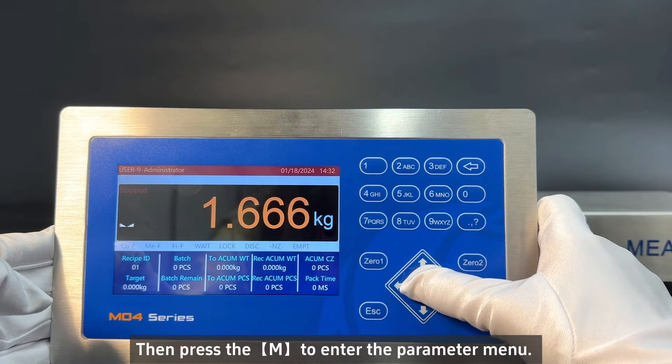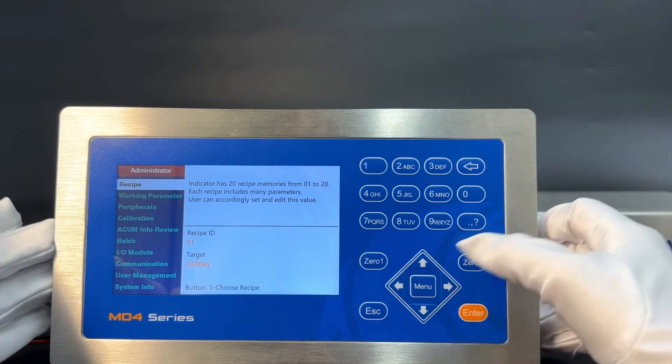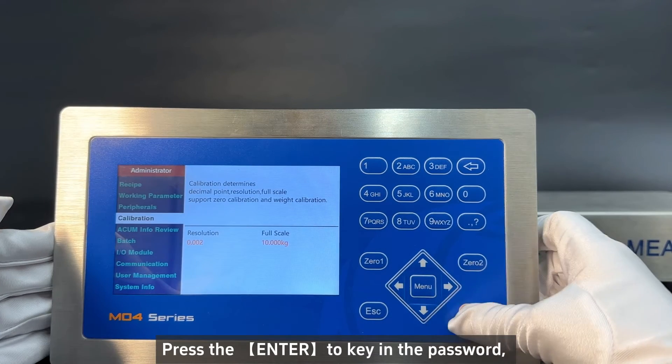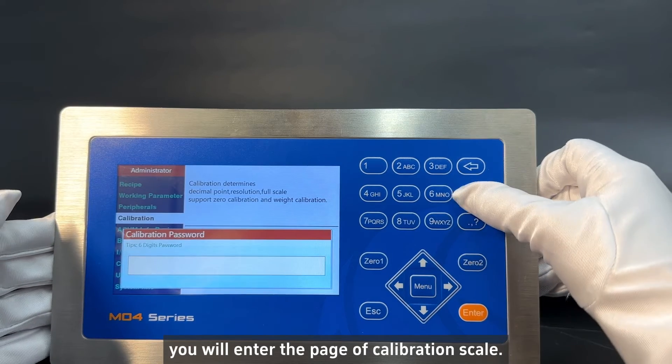Then press the M to enter the parameter menu. The calibration can be found in the left column. Press the enter to key in the password. You will enter the page of calibration scale.